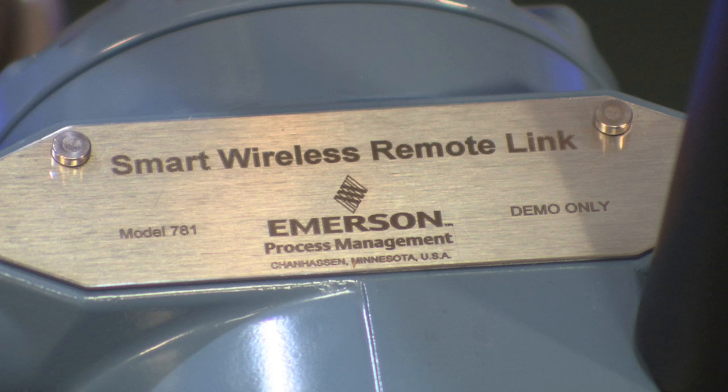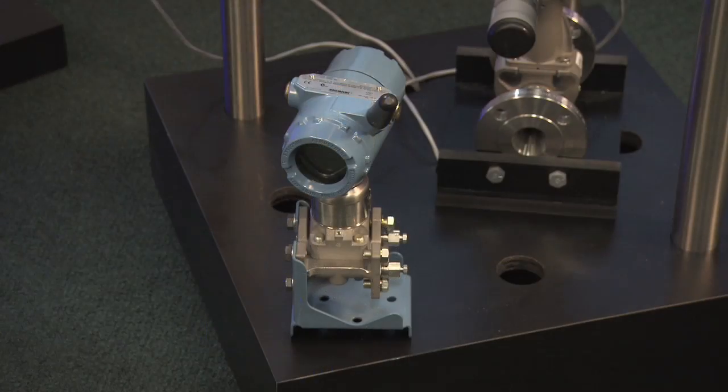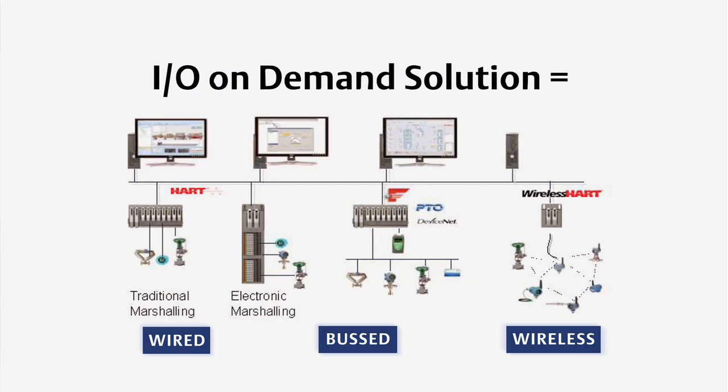So with the smart wireless remote link, which can be mounted in a zone zero part of your facility and can communicate to any WirelessHART device, you now have a fully redundant solution — all the way from the device, through the remote links, through the wireless I/O card, up to the controller. This provides another pillar in the I/O on demand solution, where you can have the type of I/O you want, when you want it, where you want it.